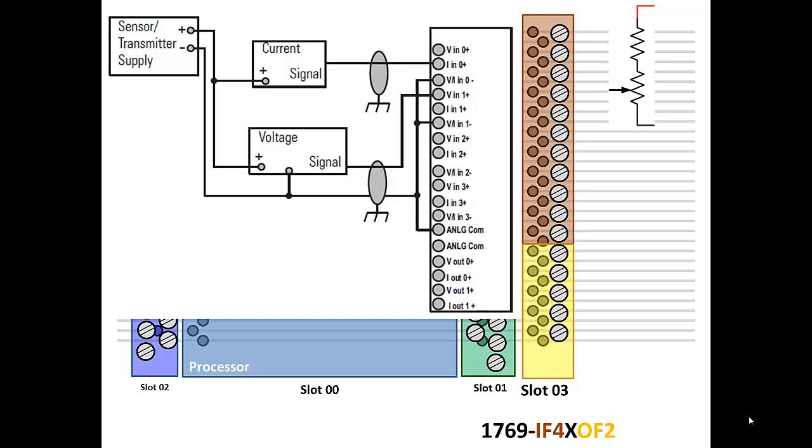The higher the total resistance, the better to keep the impedance up. However, that is a subject for another day. This type of circuit is referred to as a voltage divider. Next we will attach our 24 volt DC power supply, both negative and positive, to give us a complete circuit for current to flow through our voltage divider. This is our analog input, and you can duplicate the voltage divider up to four of these with this module. You could have four potentiometers, each giving you a unique analog input. Two is normally what I use on this type of demo.